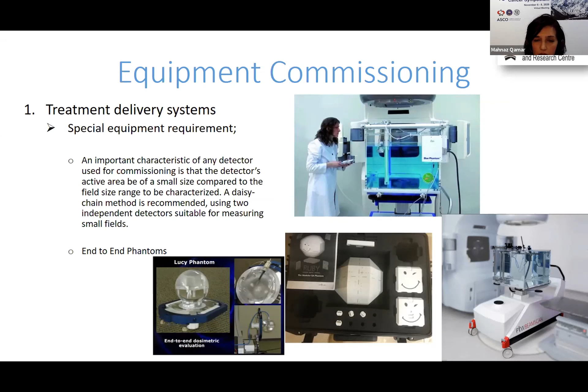A daisy chain method is recommended using 2 independent detectors suitable for measuring small fields. What that means is that you would use a regular volume detector to measure, let's say, field sizes 10 and above, and then a small volume detector to go back from 10 or even 12 or 15 and go all the way down to 2 by 2 or smaller fields. And then we have these end-to-end phantoms. A lot of manufacturers provide those, and they're used to validate the process from the beginning to the end, let's say from the patient CT to the MR, treatment planning and delivery.